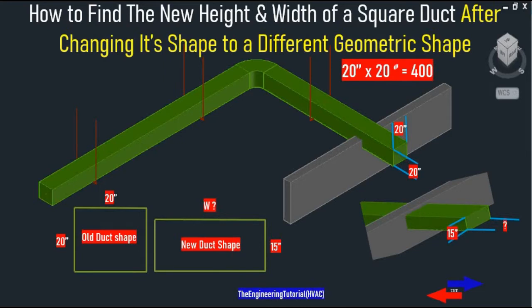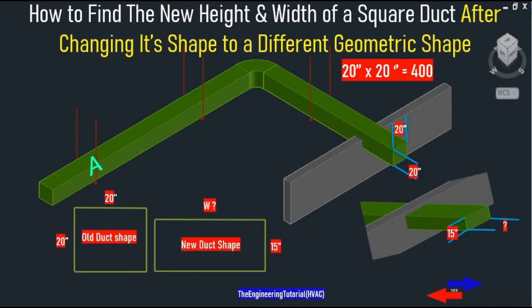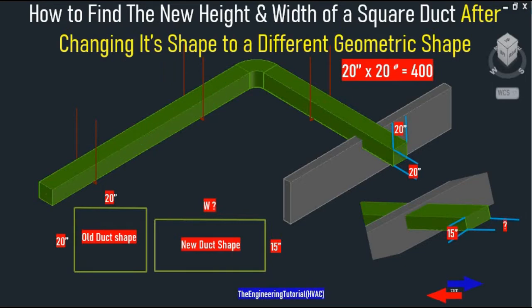For example, there is a flow rate of 3400 CFM flowing at a friction loss of 0.1 inch of water column through a square duct which has an area of 20 inches by 20 inches. For some reasons, we don't have enough space for the height of our duct, and we want the height — which is 20 inches — to be reduced to 15 inches. We still want the same amount of airflow, 3400 CFM, to be delivered through 400 square inches of ductwork after the reduction in height.